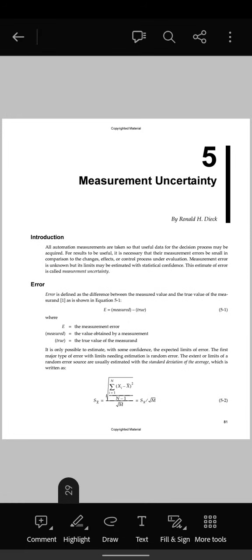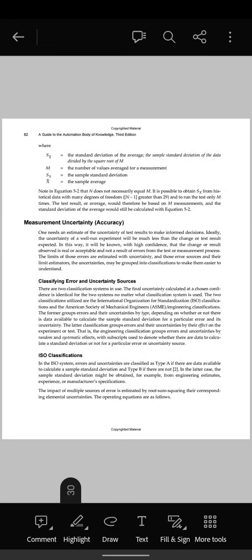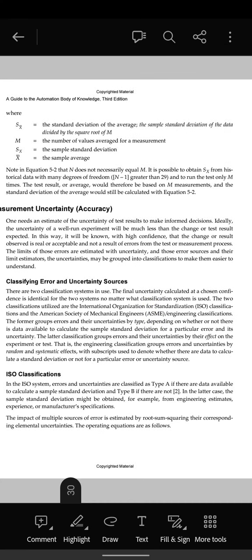The first major type of error with limits needing estimation is random error. The limits of a random error source are usually estimated with the standard deviation of the average, as written in A Guide to the Automation Body of Knowledge, Third Edition, where the standard deviation of the average is the sample standard deviation of the data divided by the square root of M, the number of values averaged for a measurement. This is equation 5.2, and note that N does not necessarily equal M.